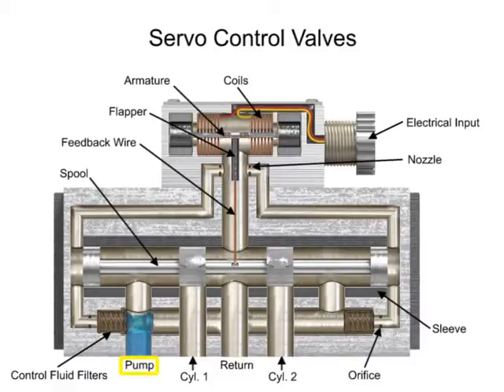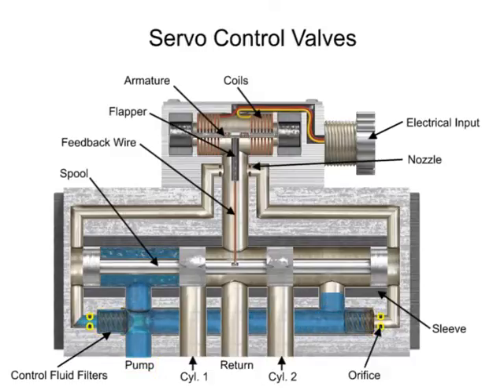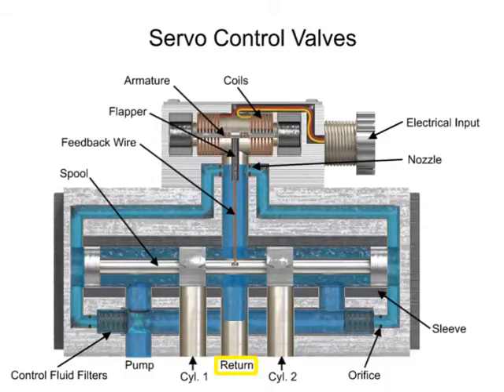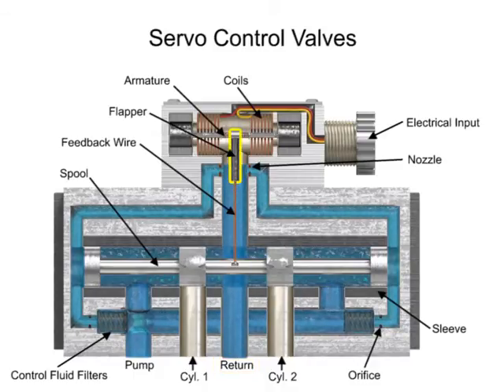Fluid from the pump inlet is tapped off through filter elements, passes through orifices past both ends of the spool, goes on to nozzles, and out to the return line. A feedback wire attached to the flapper terminates in a ball end that sits in a very close-fit slot in the spool.